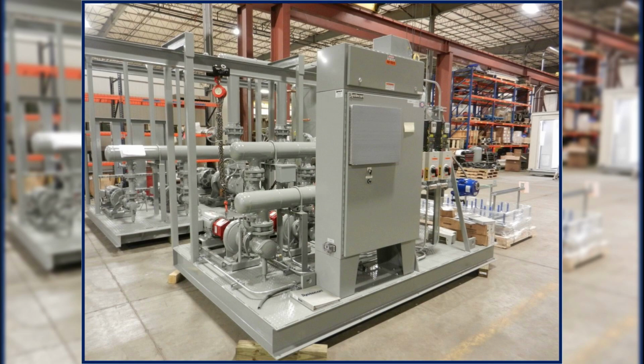For instrumentation, each package includes pressure gauges on both suction and discharge, thermometers with stainless steel thermowells, and controlled taps for monitoring. And finally, on the controls and integration side, the OEM controls take care of sequencing for chilled water pumps, while the TCC manages the hot water pumps. Both are fully integrated into the BACnet building management system for seamless operation.